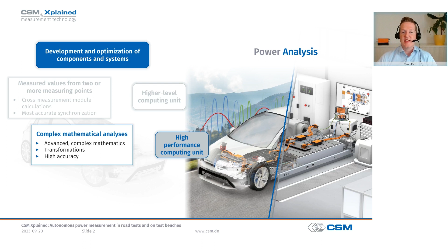Power analysis usually also includes applications in which highly dynamic processes are investigated, such as motor run-ups, which require dynamic and automatic period detection of voltage and current signals, or in which short integration intervals are required. For this, again, we need, in addition to high-speed measurement technology, a very powerful computing unit on a meter level.